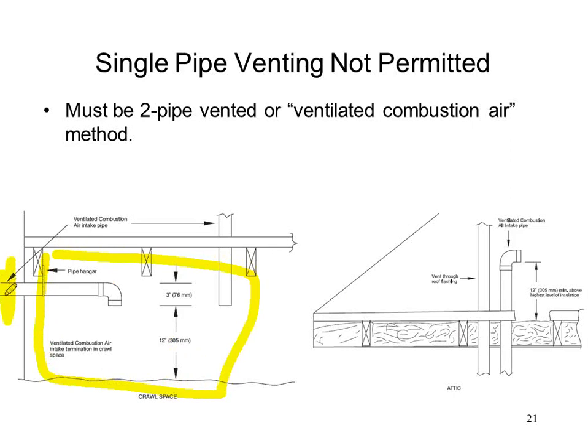So the furnace is over here somewhere, and we have the intake pipe coming from the crawl space instead of coming directly from the outdoors. And the crawl space has to be ventilated, obviously. Should go without saying, but I'll say it anyway. The other choice is the attic, right? The attic is another space that could be ventilated. So I have the exhaust pipe leaving the furnace and going all the way out of the house, penetrating through the roof.